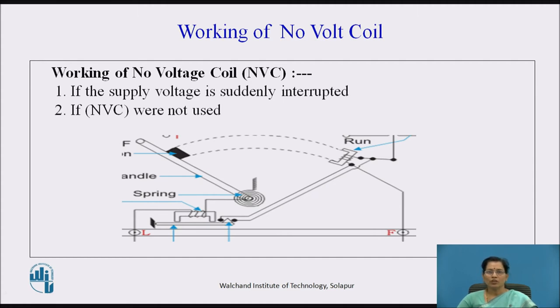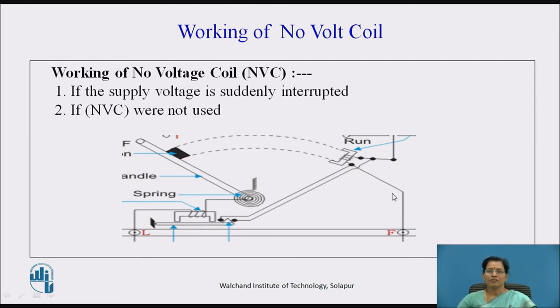If the no-volt coil were not used, what would happen? Then this arm remains at its position, and when suddenly the supply comes back, the total voltage is connected across the armature winding, and very large current flows through the armature winding, and the armature winding may burn. So for that reason, the no-volt coil is used in the starter.